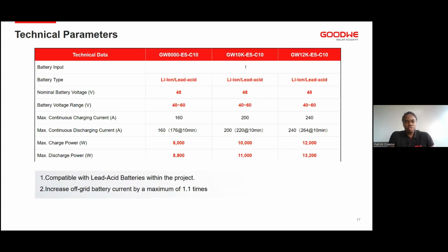Technically, let's dive a bit into the technical parameters. ES Unique is compatible with 48 volts low voltage battery systems. It comes with a wide battery voltage range, 40 to 60 volts, compatible with lead acid batteries and various approved lithium-ion batteries, and can charge and discharge at respective inverter ratings. You can see we have charging at 8, 10, and 12 kilowatts.